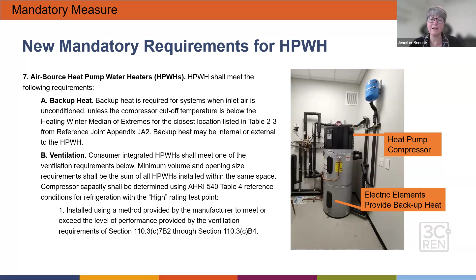And then the tank needs plenty of air volume to have the air available to extract the heat out of the air to put it into that hot water. And so that's spelled out a little bit more. The way it's spelled out might give you a little pause for thought, because they say you need the greater of 100 cubic feet per kBTU per hour of compressor capacity, or the minimum volume provided by the manufacturer.